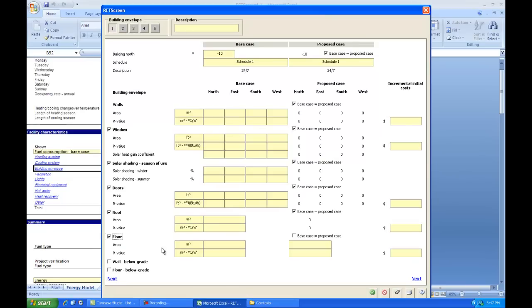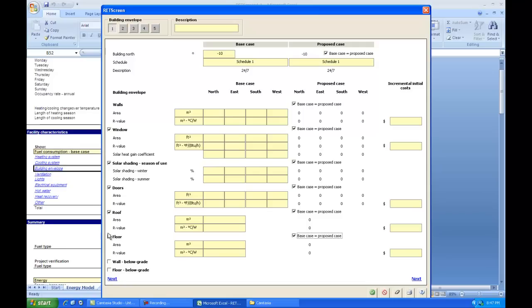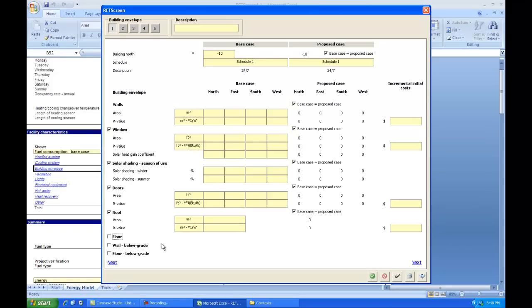Floors are frequently misunderstood. In RETScreen, a floor means a cold floor. It's not the floor of the basement. It's not the slab on grade. It's a floor that underneath it has cold winter weather. So that would be perhaps a floor over an unheated crawl space or a floor of a building that's up on stilts, the area underneath a bay window that extends out over the foundation, or a bedroom floor above an unheated garage. So if it's above unheated space, then we will model it as a floor. If it's not above unheated space, we don't have a floor, oddly enough. So with a normal ordinary house with a basement and nothing else special going on, we don't have any cold floors.